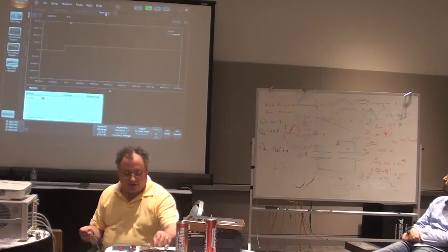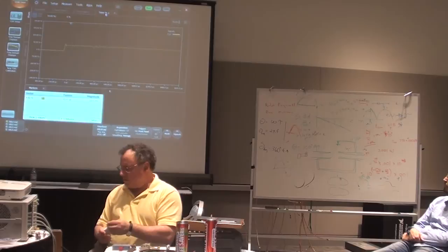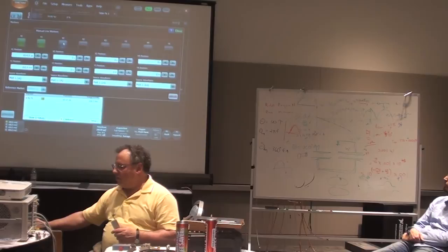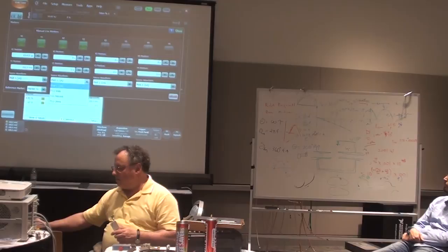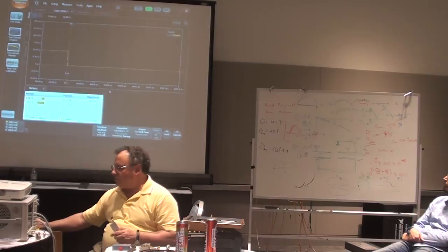And let's just do that. Let's put the short circuit back on. See that now. It turned the averaging way up again. I think. Because this is an open circuit. Where's my short circuit? Here's the short circuit. And remember. We have markers here. Which is the marker button. When that thing comes up. Let's see. Where do I want to put markers? I want to put markers on the ohms scale. Put it on the ohms scale. And you can mix and match your markers.